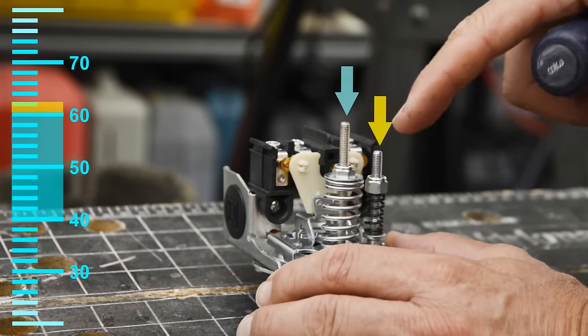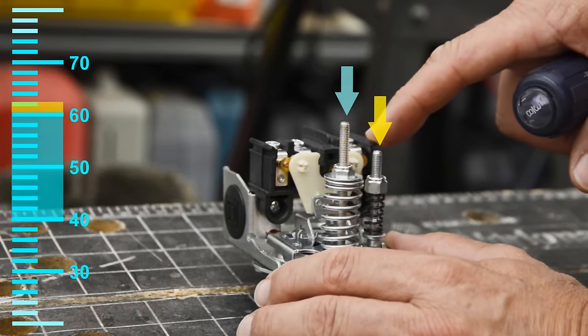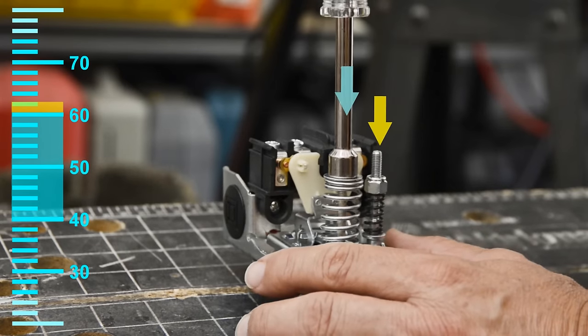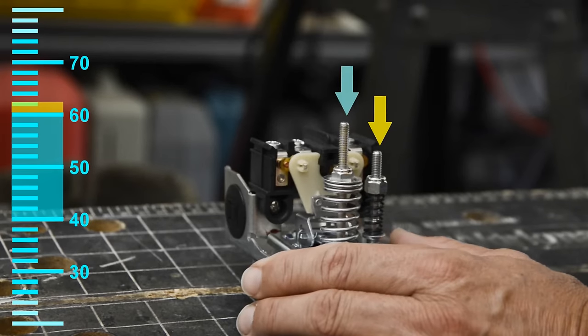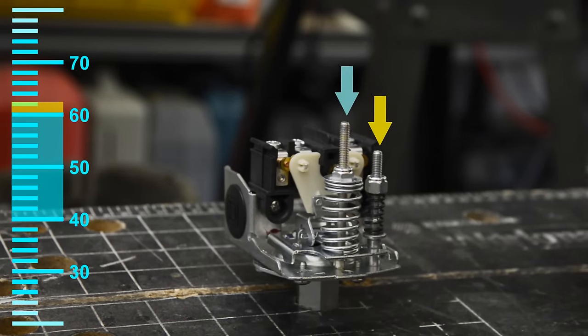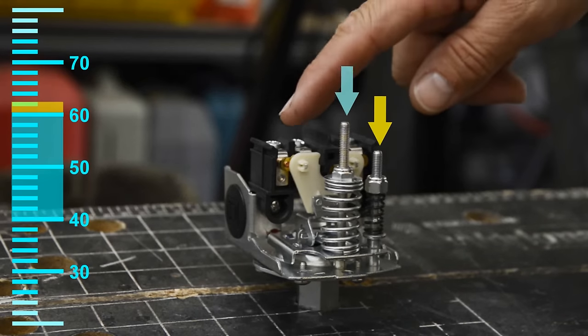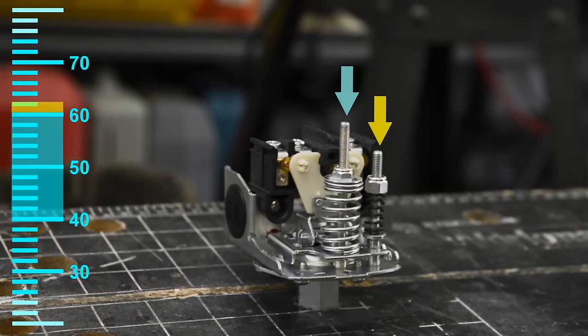We're going to show you how the contacts open and close, and where they open and close at. So I'm going to tighten it down three or four turns, and then I'm going to increase the pressure until it cuts off, and you'll notice it opening the contacts.